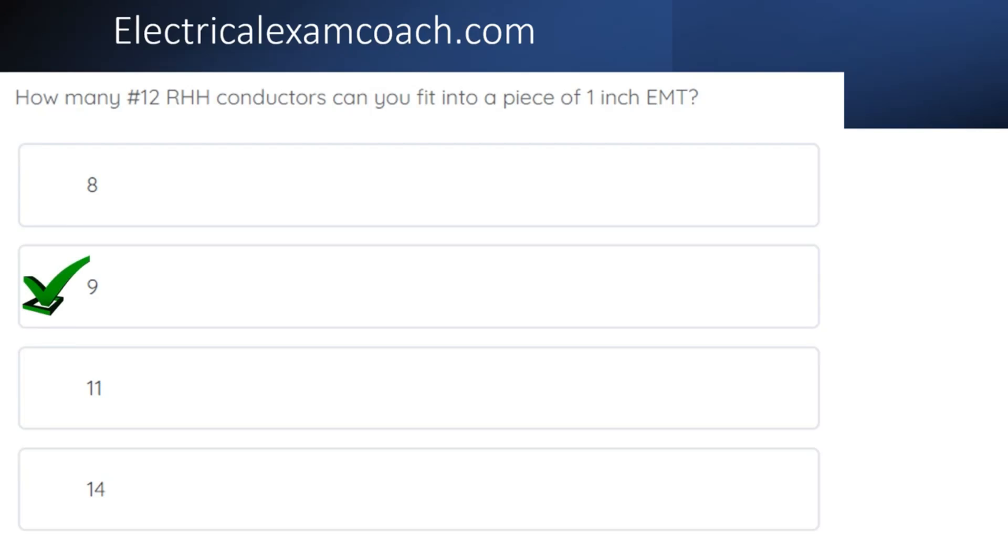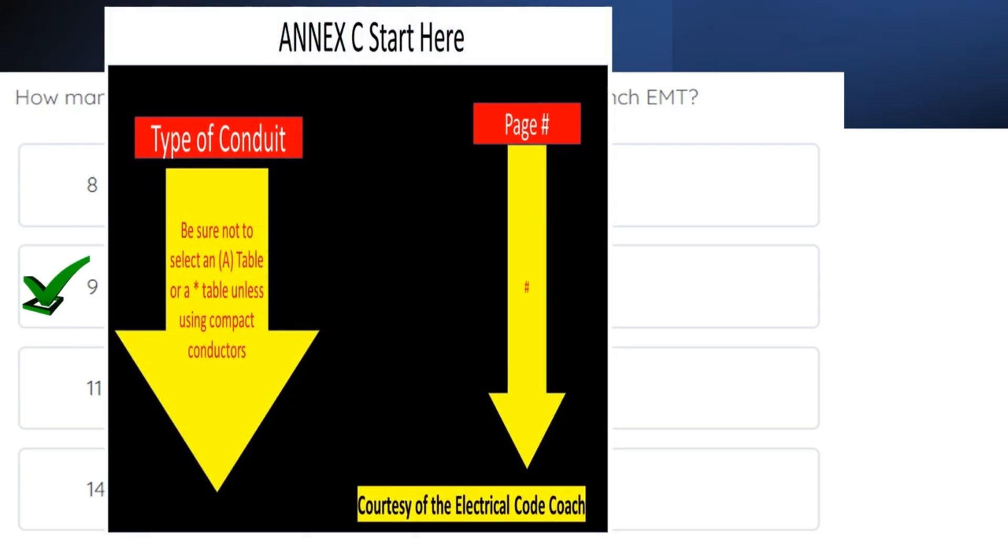We're going to start this process out at the beginning of Annex C. At the beginning of Annex C, it's going to list our type of conduits and the page number that they're on. We're going to be sure not to select an A table or a star table unless we're using compact conductors.